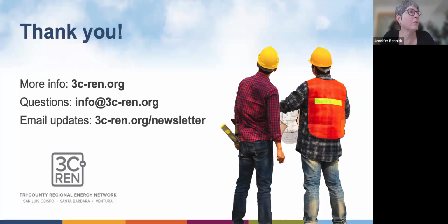Thanks, Danica. There was one question I answered partly in the chat, but the question was wondering about dealing with the condensate line off of those indoor mini split units and where it goes and what we do with it. Generally speaking, on the projects we've worked on that are additions and remodels, where you're installing the systems after the structure's been built, for those indoor units, you're going to make some kind of penetration through the envelope, through the wall.